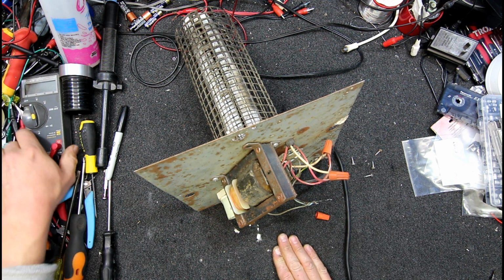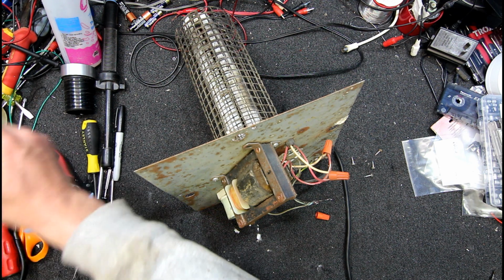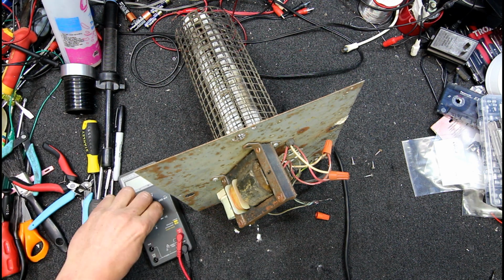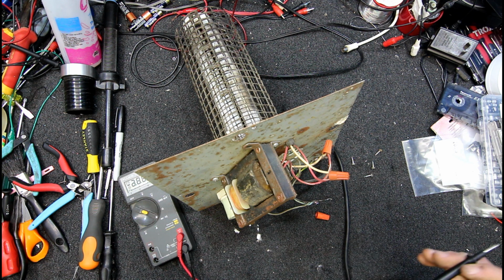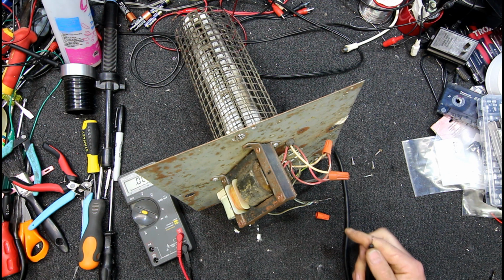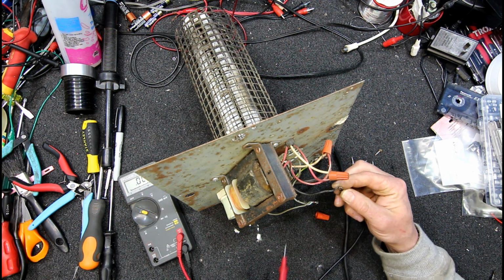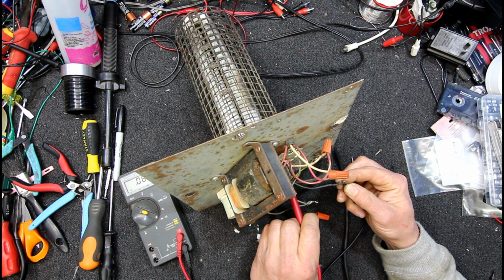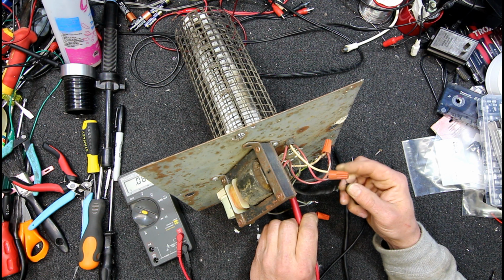Well, to be fair, the ballast is probably open circuit anyway. I'm thinking the starter will be across it, but the ballast is in series with the lamp, so with an open circuit starter and an open circuit lamp, which a lamp is until it conducts, we should... so that sounds like it's good.